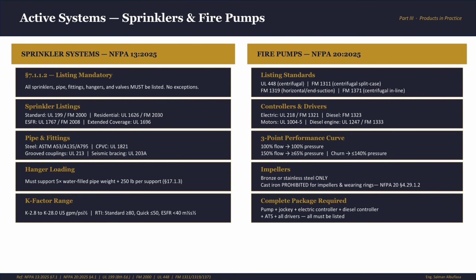So now my sprinkler system is not enough. It might have been before, but not for this hazard. The heads aren't the right K factor. The water density is not sufficient. Now I wait for a fire to happen so I can learn my lesson the hard way. This is the most common and most overlooked compliance failure in practice. It's everywhere, in every region. So, occupancy change requires a full reassessment of the suppression system, no matter how expensive it is, no exceptions.